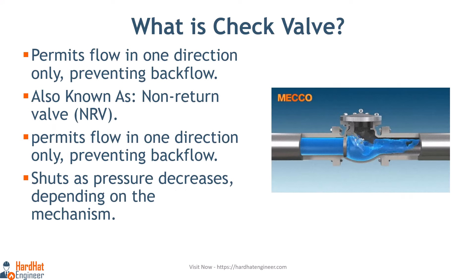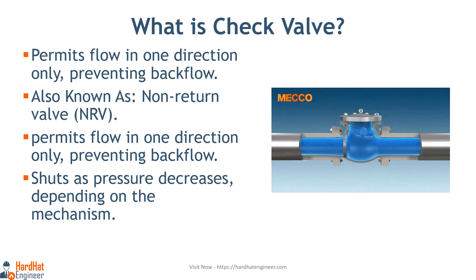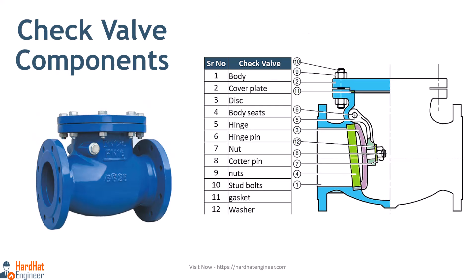What is a check valve? Check valves permit flow in one direction only, preventing backflow and ensuring unidirectional movement of fluids in pipelines. It is also known as a non-return valve or NRV. The pressure of the fluid passing through a pipeline opens the valve, while any reversal of flow will close the valve. It allows full unobstructed flow and automatically shuts as pressure decreases. It consists of the body, cover, disc, hinge pin, and seat ring.